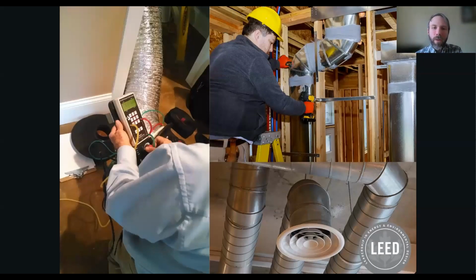All right, continuing with some more of the requirements. Leaky ductwork reduces energy ratings, increases utility bills, and can often lead to discomfort and reduce occupant health. Now, LEED is the most sustainable here because they require low duct leakage through a test, with exemptions for multifamily mid-rise units for more-story buildings when all the ductwork is in conditioned space. Enterprise requires this too, but only on new construction, and National Green Building Standards simply rewards points for this. All programs give more energy points in the energy ratings, typically when duct leakage is reduced overall. And again, here is another area where we see significant failures on LIHTC projects.